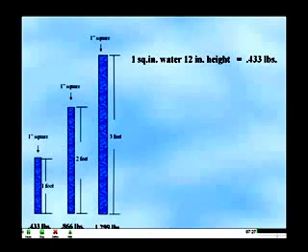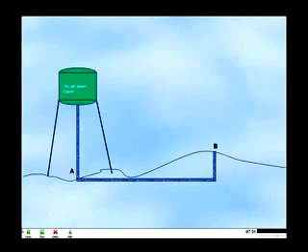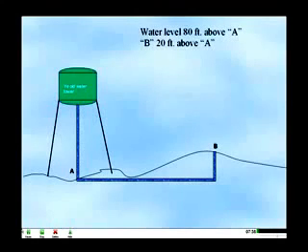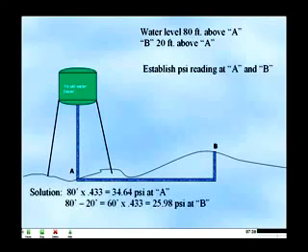To illustrate this principle, this water tower is 80 feet high. Using the formula discussed previously, water pressure at the base of the tower will be 34.6 PSI: 80 times 0.433 equals 34.6. However, the PSI at point B will be 25.9 PSI: 60 times 0.433.